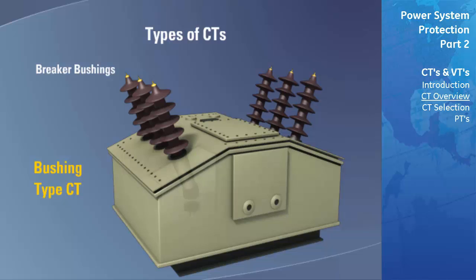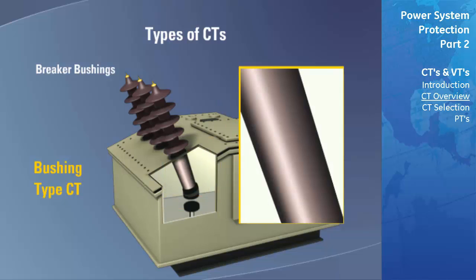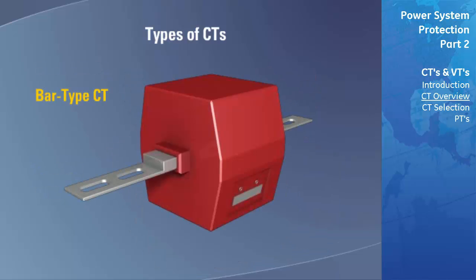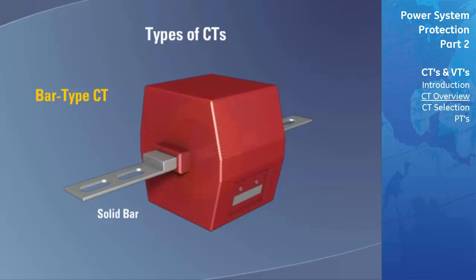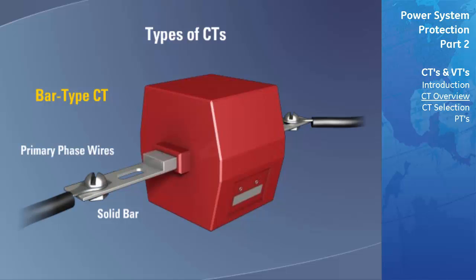A bushing type CT refers to a CT that is built into another power system device, such as a breaker. Terminals are provided on these devices to permit connecting the CT to a relay. A bar type CT has a solid bar that passes through the annular core to form the primary winding of the CT. The primary phase wires of the power system are then connected directly to these bars to complete the connections.